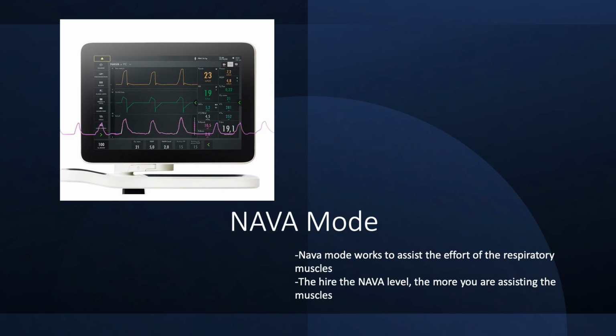So once you place a NAVA catheter in a patient, and you've ruled out that you have no activity from the cardiac system, and you are picking up the electrical activity from the diaphragm, this is kind of what the screen looks like. So in this patient, you can typically start by overlaying the electrical activity of the diaphragm over your pressure waveform. If you see that you're missing triggers or your end exhalations are off, then it would probably be beneficial to go to NAVA mode on a spontaneous breather. Here you can see that the top waveform has a pressure, which is in yellow still. The green's flow. It looks like it has the volume missing, but it would be there. And it looks like they're exaggerating the purple here, which is the NAVA activity.